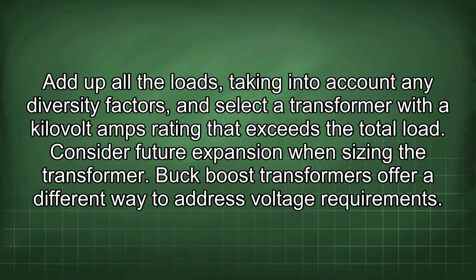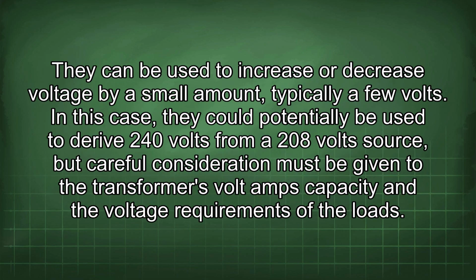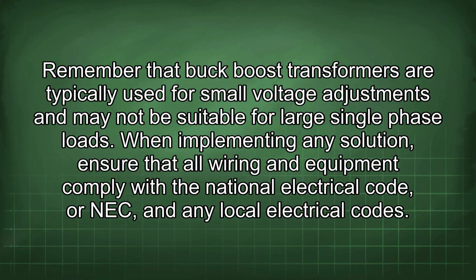Buck-boost transformers offer a different way to address voltage requirements. They can be used to increase or decrease voltage by a small amount, typically a few volts. In this case, they could potentially be used to derive 240 volts from a 208 volt source, but careful consideration must be given to the transformer's volt-amps capacity and the voltage requirements of the loads. Remember that buck-boost transformers are typically used for small voltage adjustments and may not be suitable for large single-phase loads.